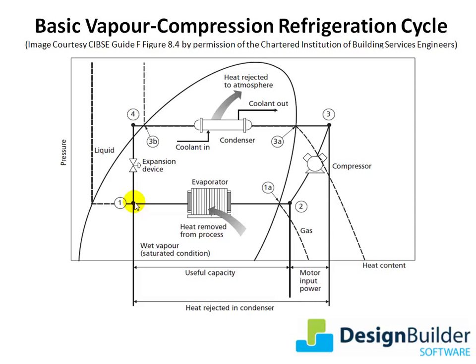In the chilled water loop, all these components may be included within the chiller. However, direct expansion systems such as split and packaged units may have these components in different locations, with the evaporator as the room terminal unit absorbing heat, and the condenser unit located externally rejecting heat to the outside air. This cycle may also be reversed in a heat pump to reject the heat of compression to the conditioned space.